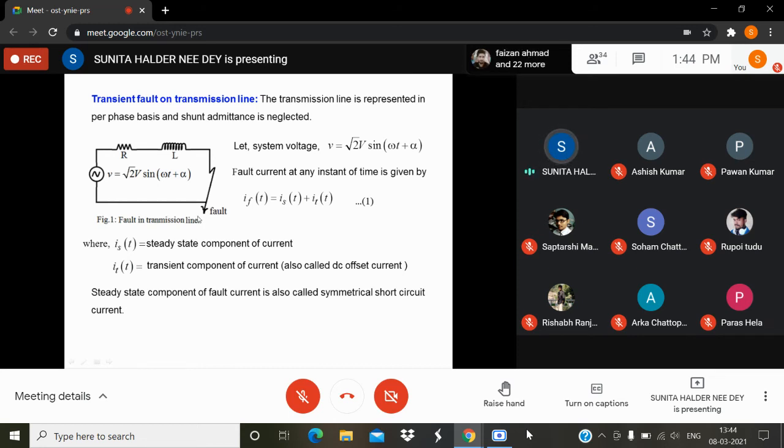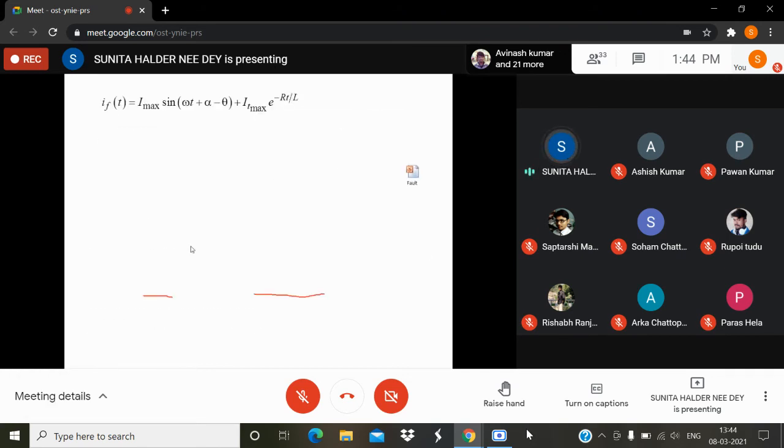So the system should be protected from this condition. Everything should be designed to face this scenario. It may happen, depending on circuit breaker speed and relay signal sending procedure, that the system is disconnected before 10 millisecond, or may not be. If it is not disconnected before 20 millisecond, then the system should withstand this current near to the double. Obviously, it will never be exactly double, but it will be somewhat near to the double.